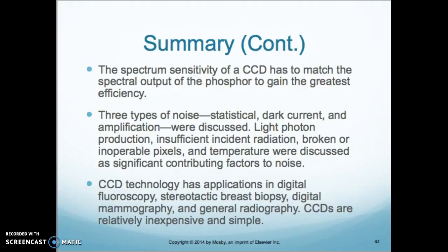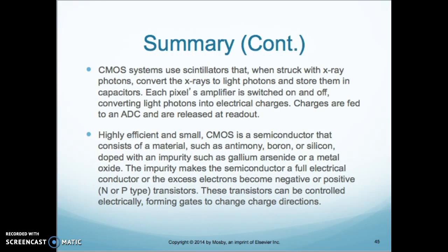CCD technology has applications in digital fluoroscopy, stereotactic breast biopsy, digital mammography, and general radiography. CCDs are relatively inexpensive and simple. CMOS systems use scintillators that, when struck with x-ray photons, convert x-rays to light photons and store them in capacitors. Each pixel's amplifier is switched on and off, converting the light photons to an electrical charge, and charges are fed to an ADC and released at readout.